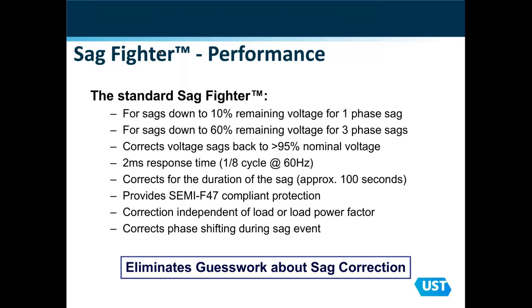So, Sag Fighter features or specifications, if you will. As I mentioned, down to 10% remaining voltage on one phase, 60% remaining voltage on 3 phases. What the product is doing is, because we don't have any energy storage, we're taking advantage of the energy left on the system to boost the phases that may need correction. So we're taking advantage of what's there. We don't need any batteries or capacitors to inject more energy into the system. We're simply taking advantage of what's there and remaining.